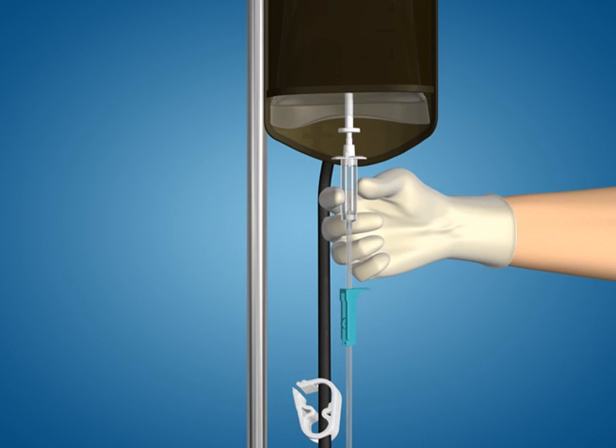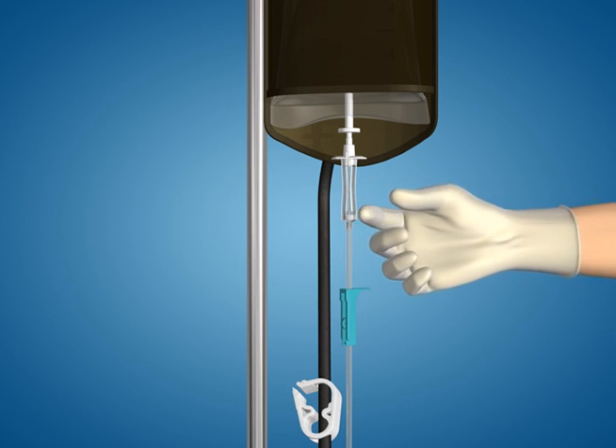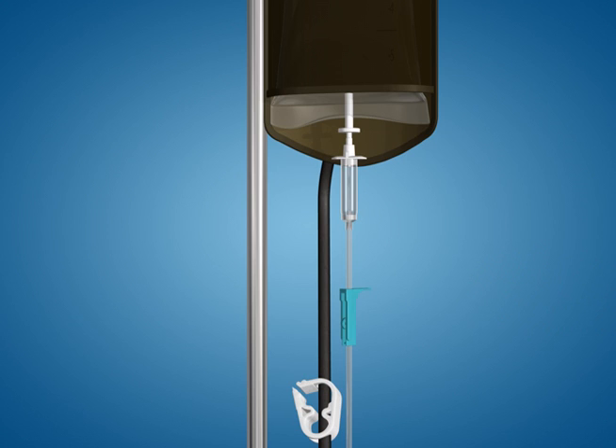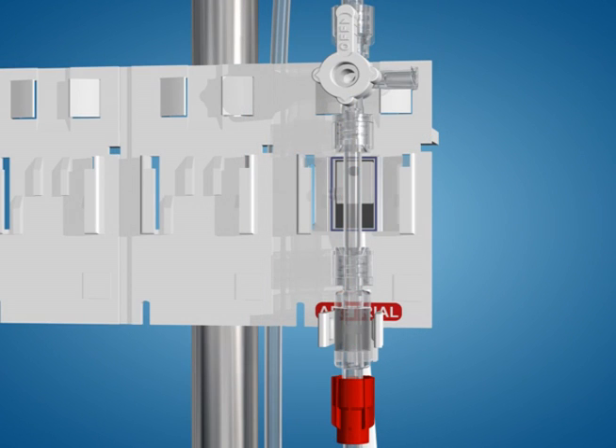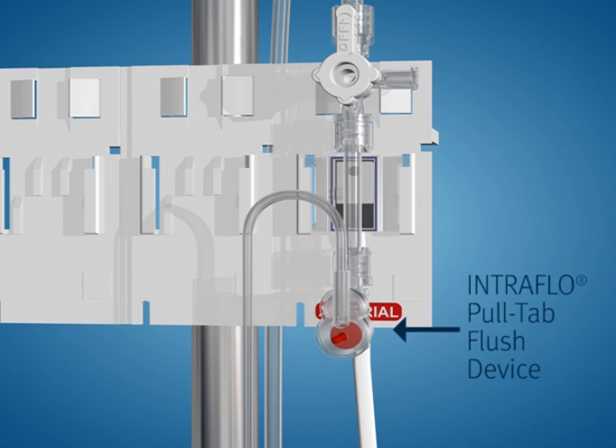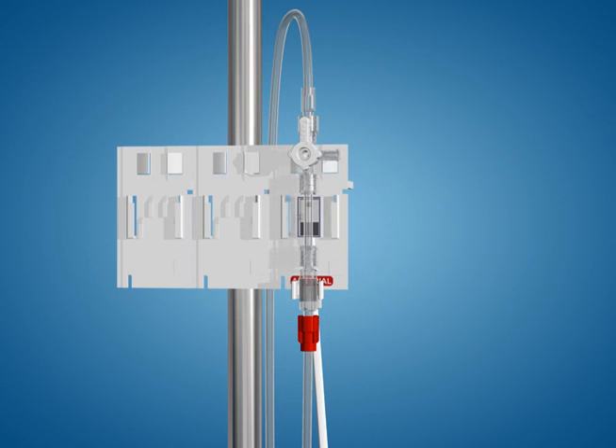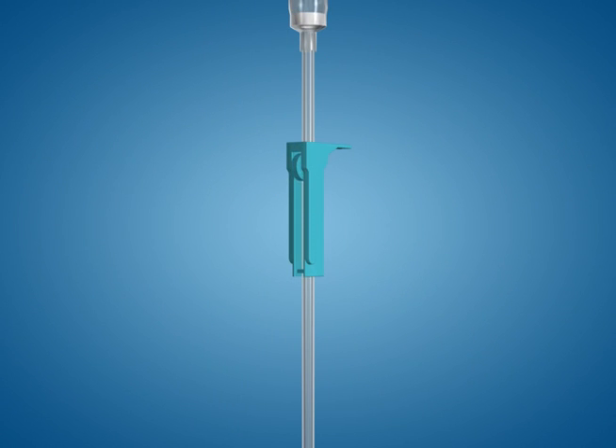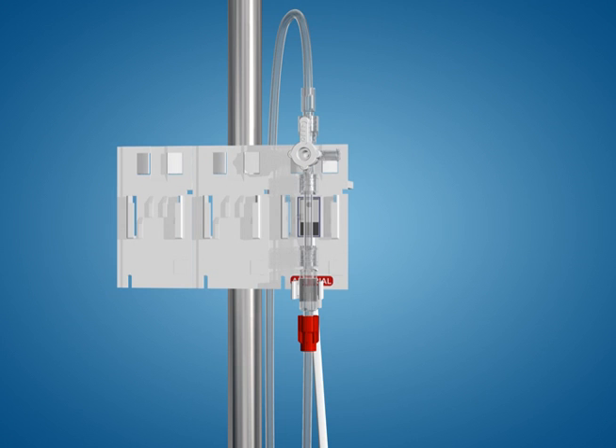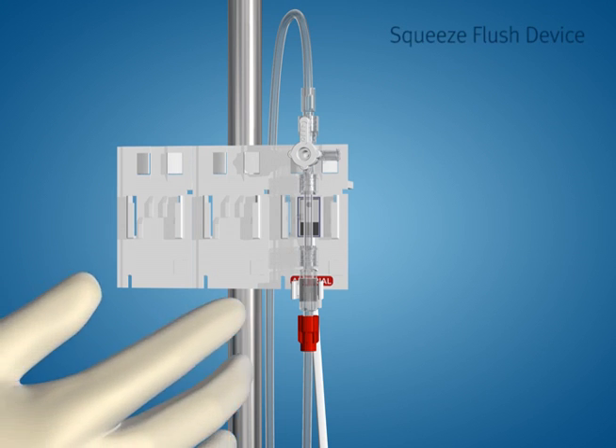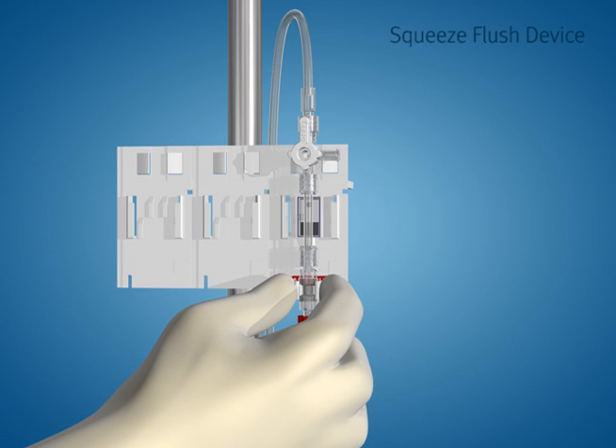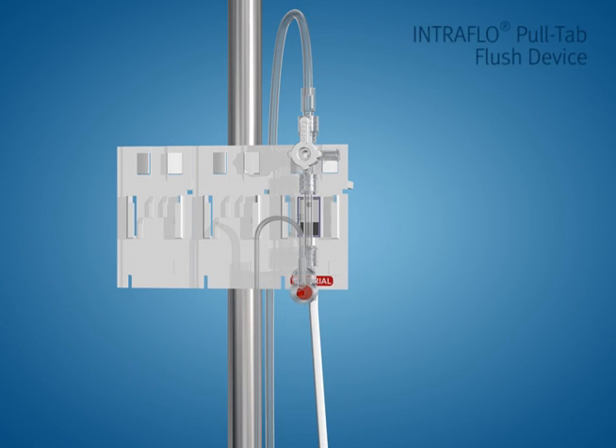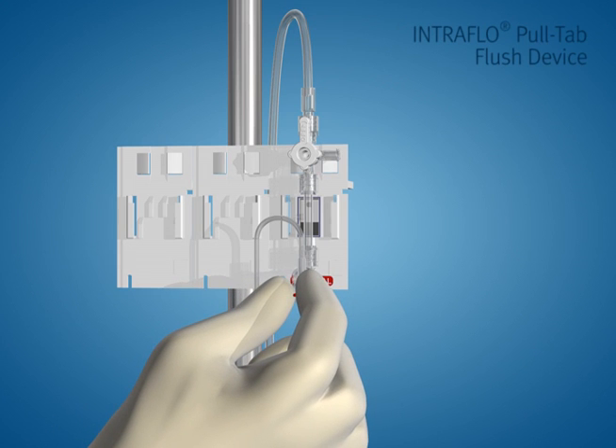With the administration set clamp closed, gently squeeze the drip chamber and fill the drip chamber approximately 1/2 full. ICU Medical offers 2 different flush device options with the Transpac transducer kits: a squeeze flush device and an INTRAFLO pull tab flush device. Now prime the line. Gravity priming is recommended. Open the roller clamp by the drip chamber and activate the flush device. When using the squeeze flush device, simply squeeze the compression tabs to activate fluid flow. When using the INTRAFLO flush device, pull the pigtail to activate fluid flow.